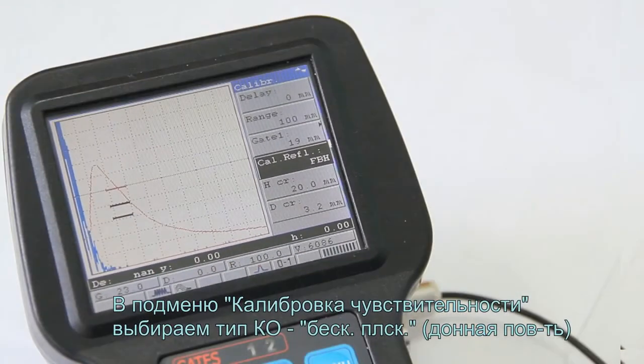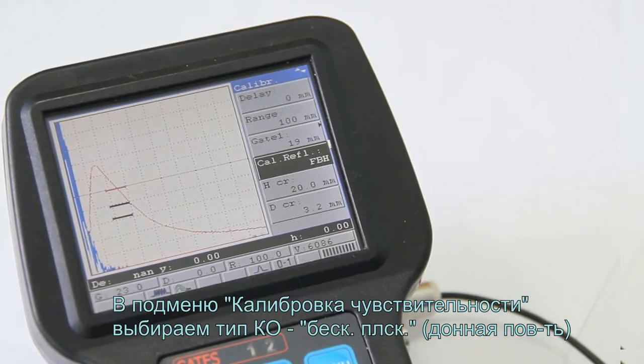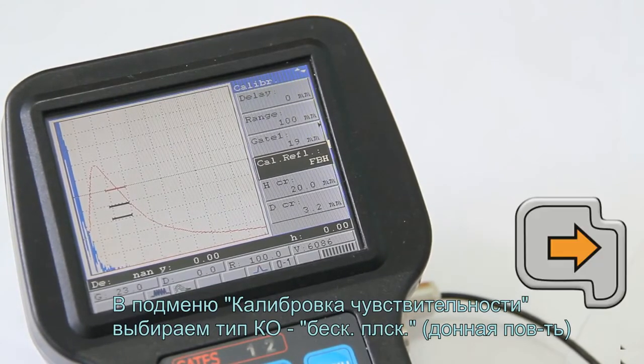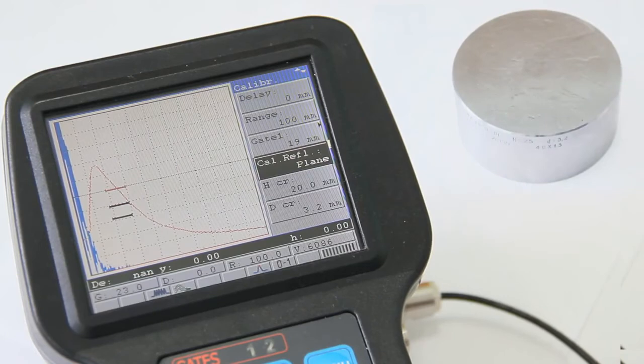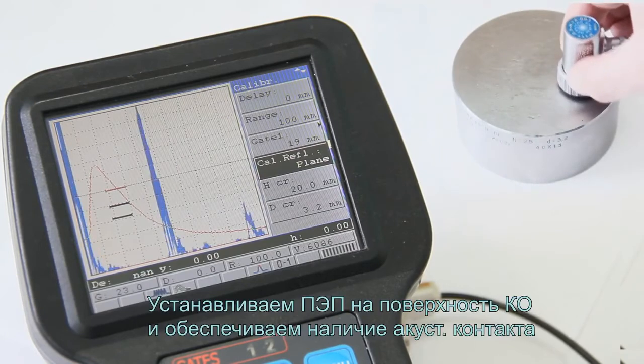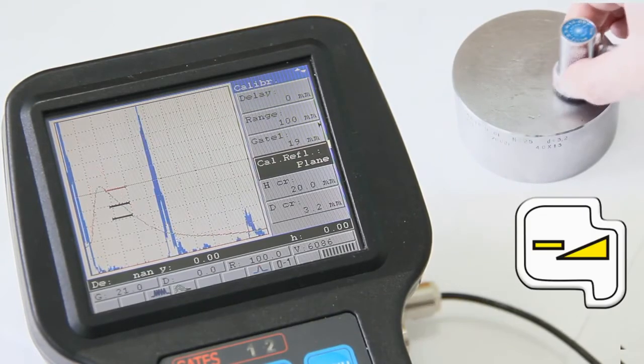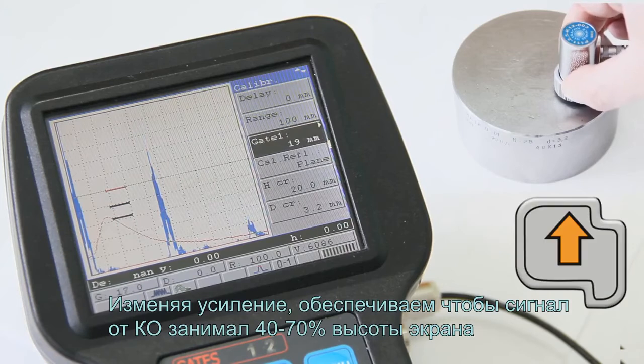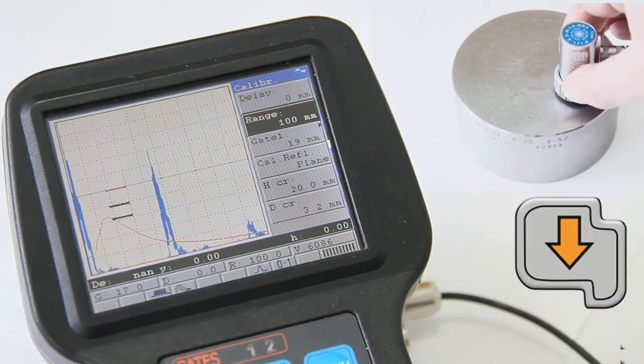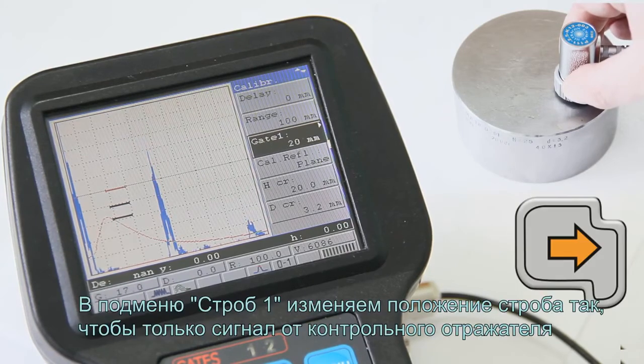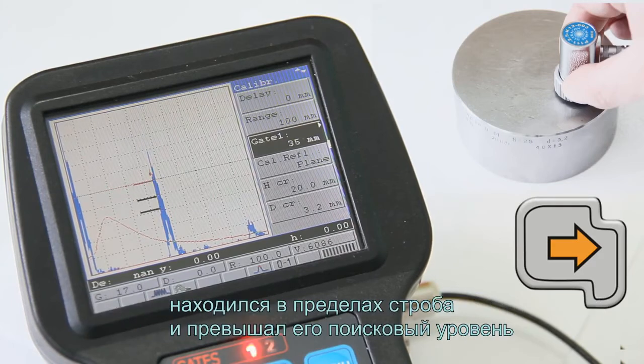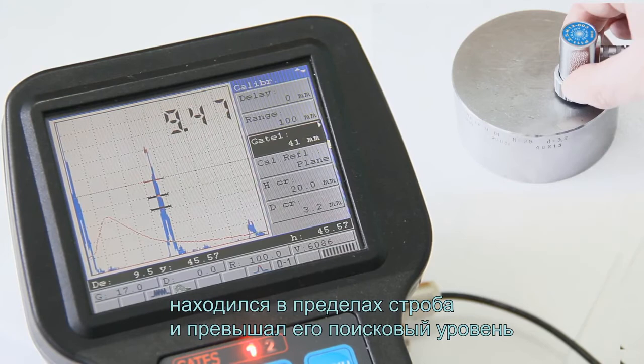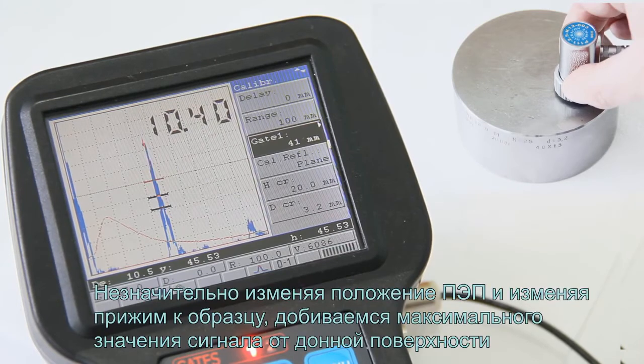In Sensitivity calibration submenu, select the type of calibration reflector, plain backwall echo. Place the probe at block surface and ensure the presence of acoustic coupling. When changing the gain, ensure the signal from the block to be within 40–70% of display vertical scale. In Gate 1 submenu, change the gate position in such a way that the signal from the calibration reflector to be within the gate and do not exceed its surge level.